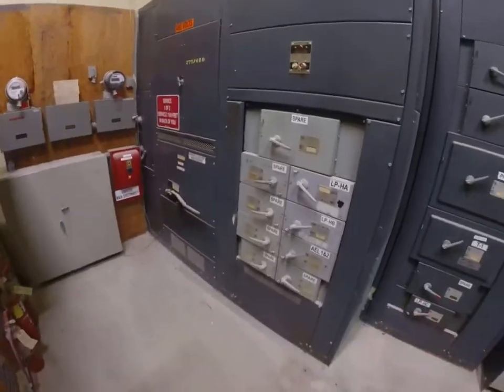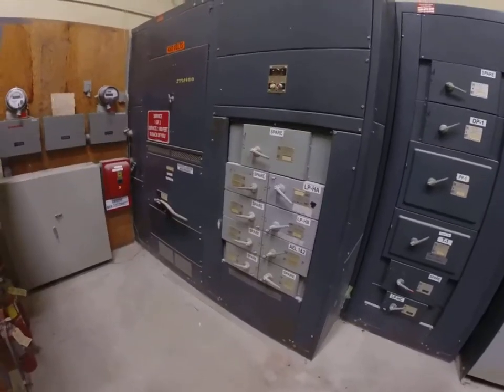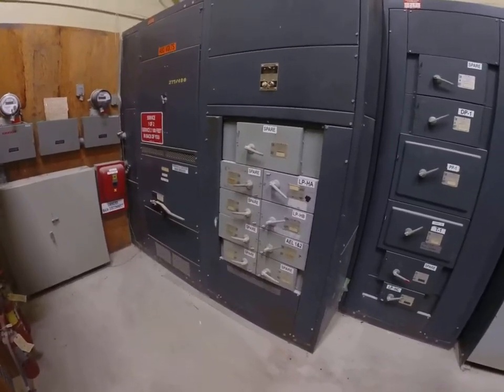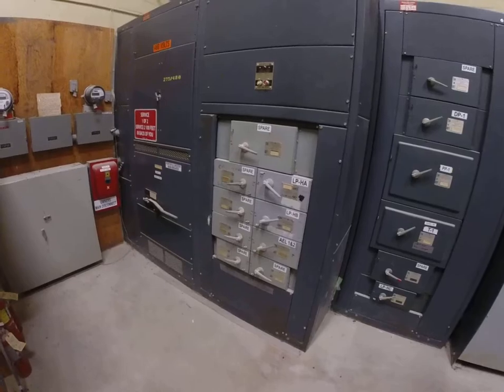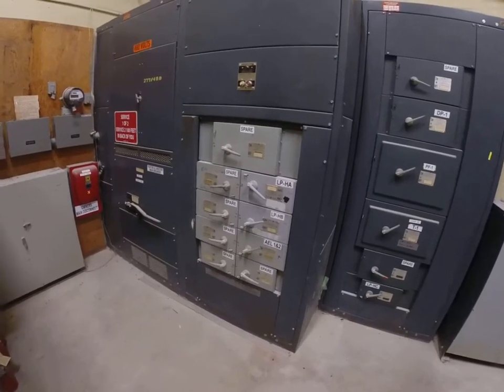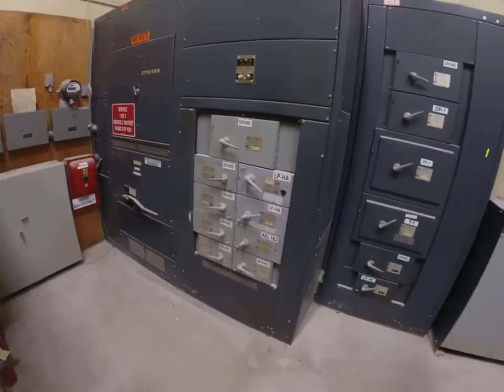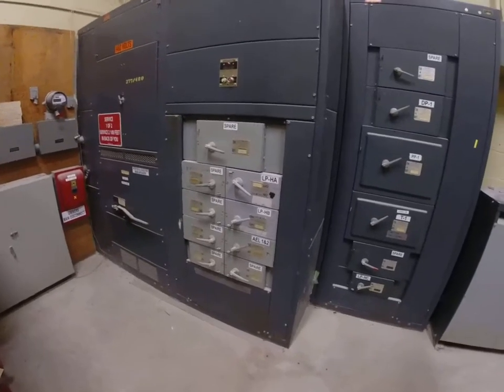In all likelihood, if I was to open up the bottom of this, we'll probably see 3 parallel sets of conduits. 3 4-inch conduits would give me my 1200 amps, 500 kcmil. That would be a typical way of doing that.